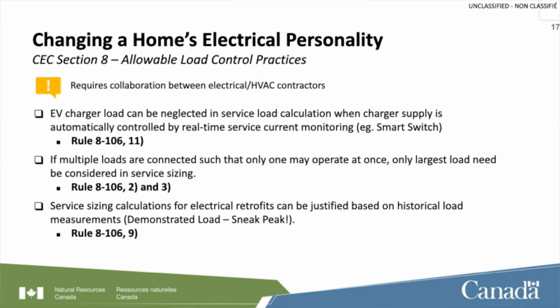One of these rules belongs a bit later down the road - these are some of the rules around electrical usage. An EV charger load can be neglected if the load's in the service calculation, if it is switched or on a real-time monitoring device - that's your load miser, smart switch. If multiple loads are connected such that only one may operate at once, only the largest load needs to be considered.